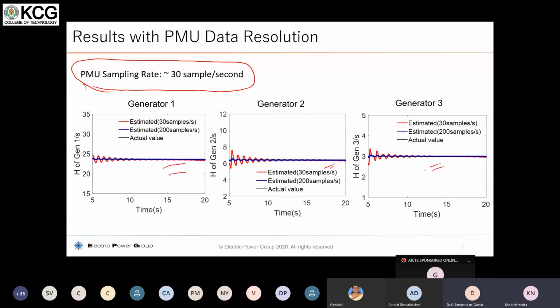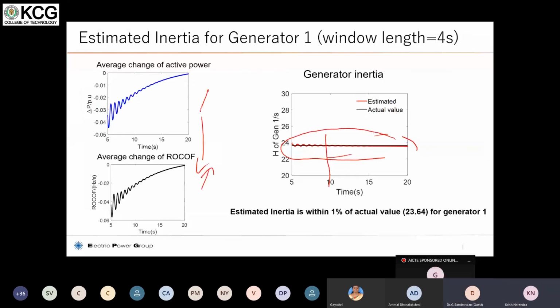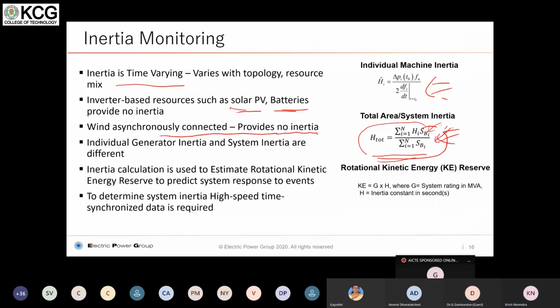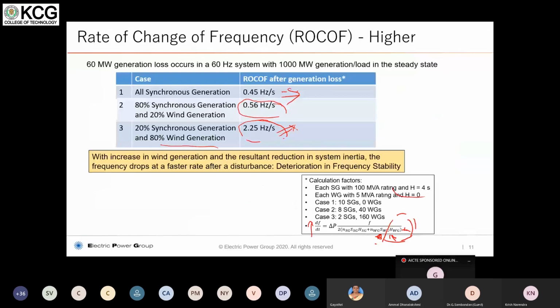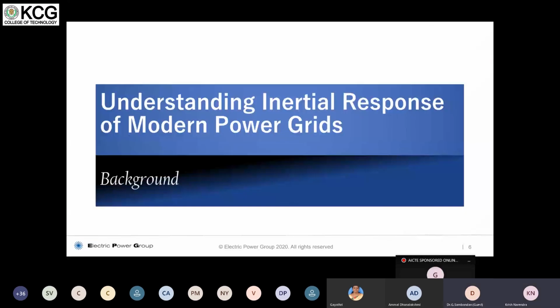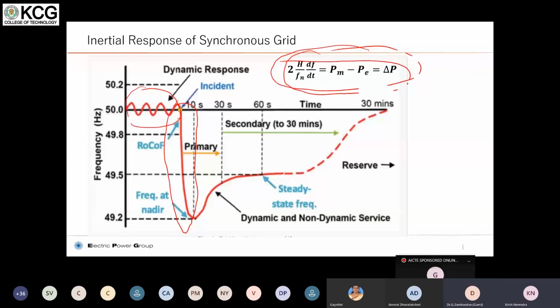If you look at the dynamic equation here, the power within the inertial response, the mechanical power will pretty much remain constant. It doesn't change. So only the electrical power changes from instant to instant. On the left hand side, if you look at df by dt, the frequency of the system, Fn and H are there, right? H is the inertia of the system, basically.